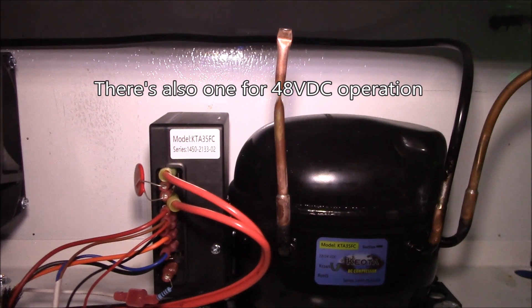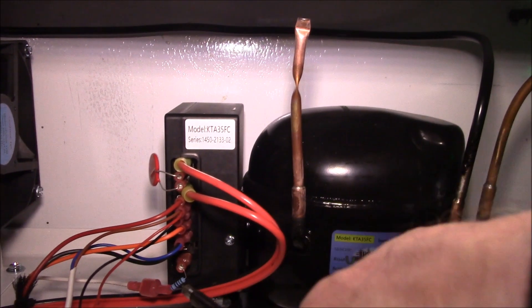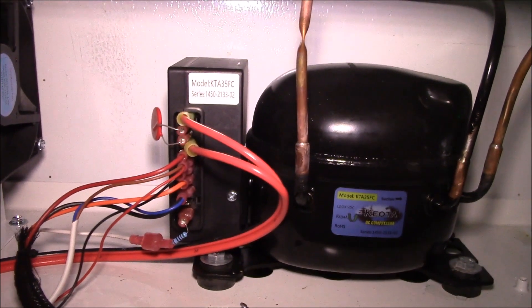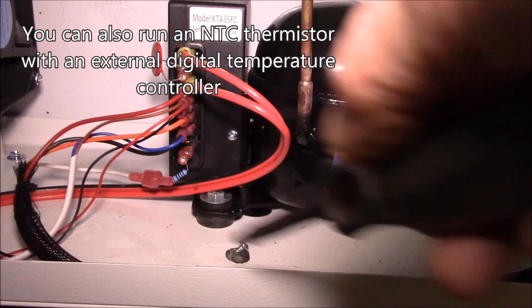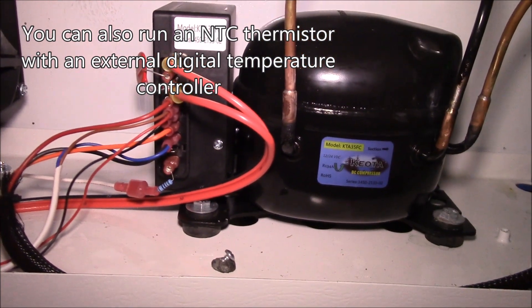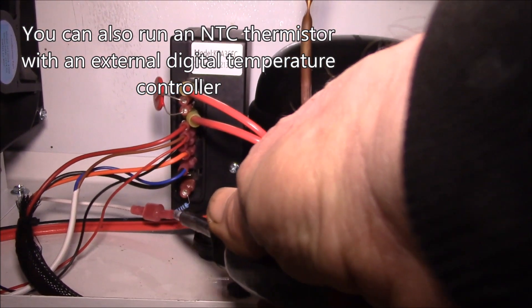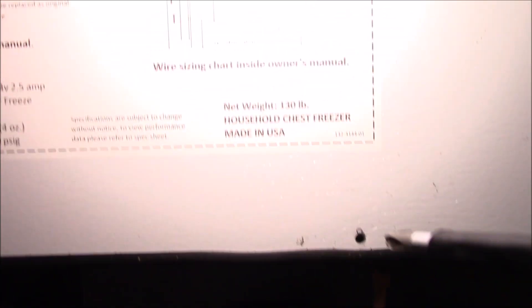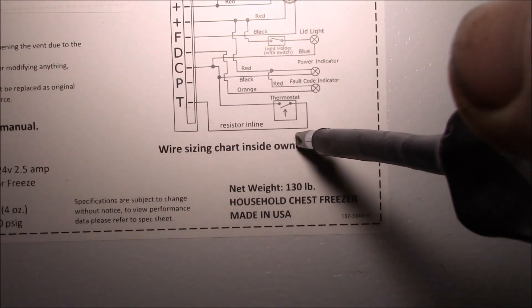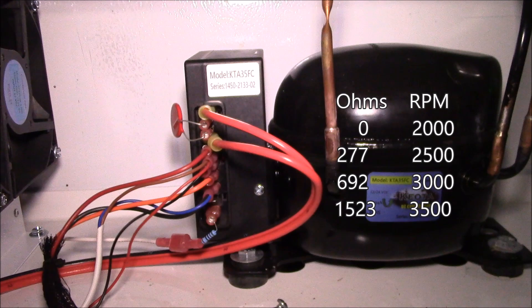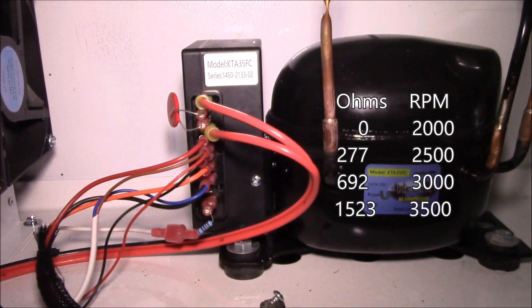There's another variation of this that has automatic speed control. This version here uses this resistor in the thermostat wire. You have a couple of options - you can just use a simple on-off thermostat like this one set up with just a bi-metal thermostat. It's got a resistor in line that you can set the speed with. The T is the thermostat and then there's a resistor in line. That resistor is 510 ohms and that results in a speed somewhere between 2500 and 3000 RPM.